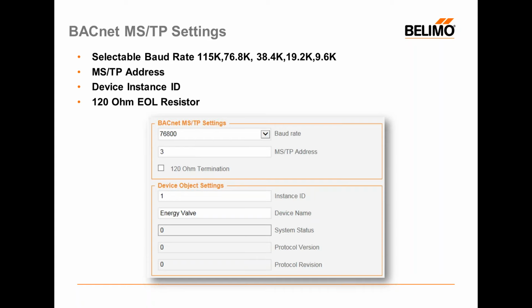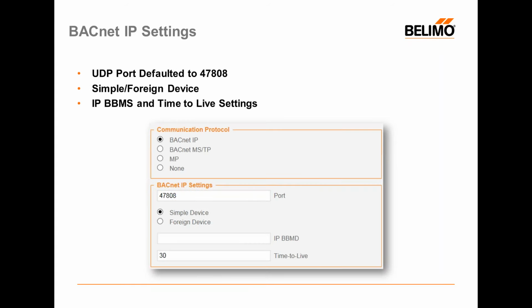Once you get into the valve's web server, you can go to the BACnet over MSTP settings and change your BACnet addresses for your BACnet network. So here you can see you can select your baud rate, provide your appropriate MSTP address and device instance. You can give the device a specific name if you'd like. And if, in fact, this is the very last device on a BACnet segment, we do have a virtual 120 ohm end-of-line resistor that can be selected.